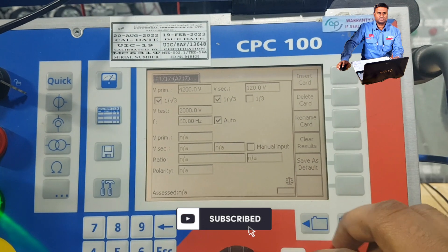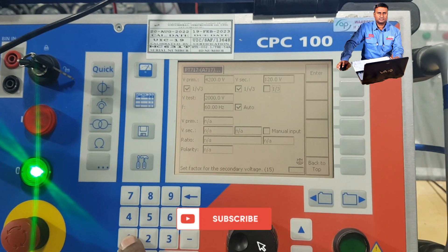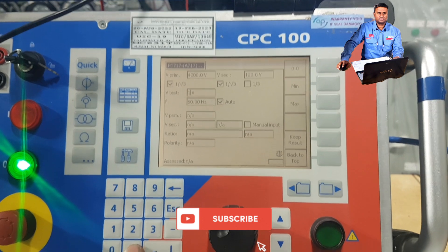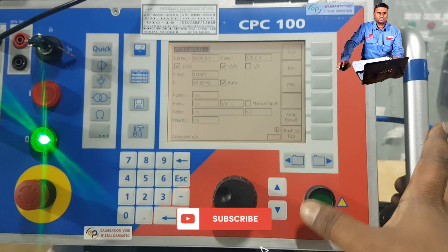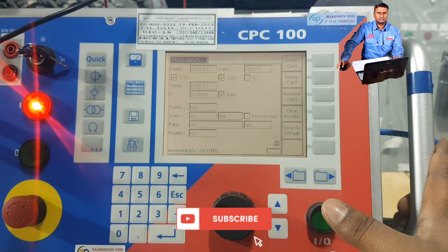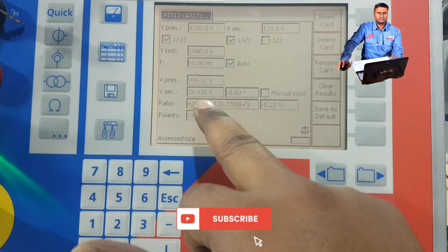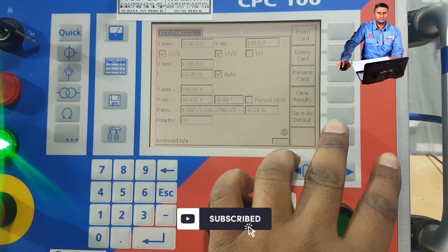To check the 1kV result, clear the previous results, go here, and inject 1000 volts. Start the test. We received 28.6 volts — according to our VT ratio it is correct, so this test is passed.